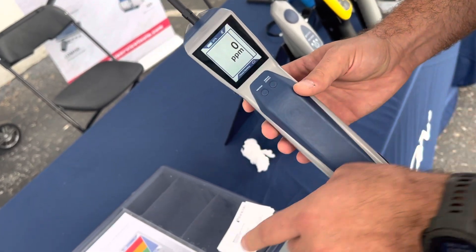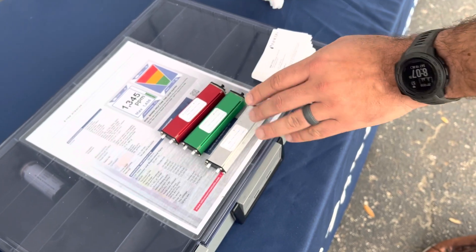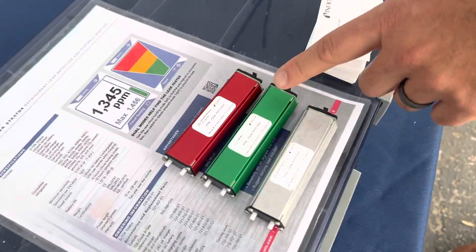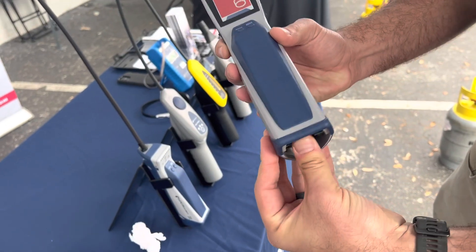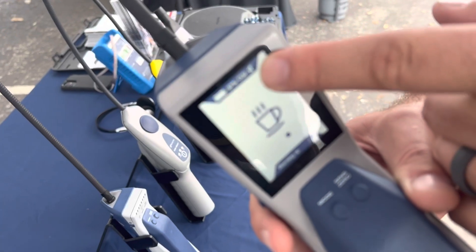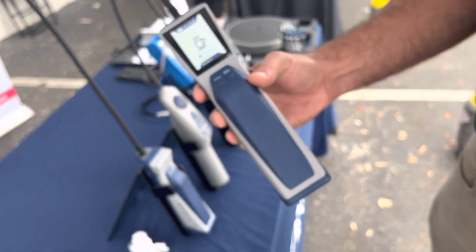The other big thing with the D-TEK Stratus is the ability to interchange infrared sensors for different applications. If you want to detect CO2, all you have to do is open up the battery door, take out your refrigerant sensor, and insert the CO2 sensor — just like that. As you can see, it reads that there's a CO2 sensor present, and after this quick warm-up we'll have sensitivity to CO2.